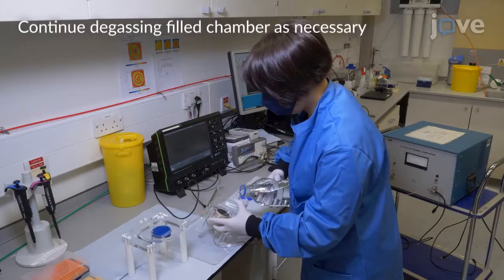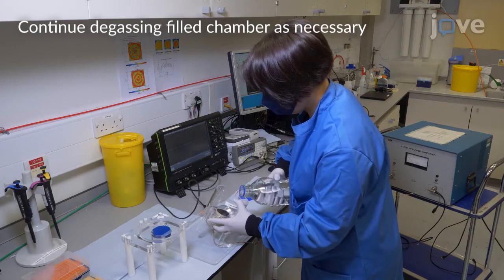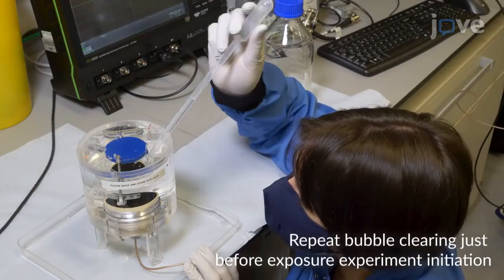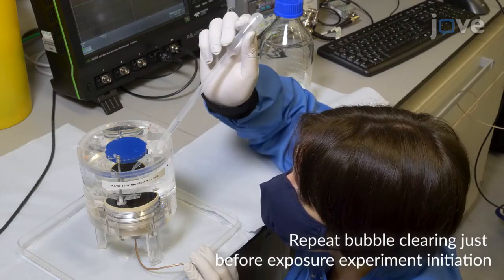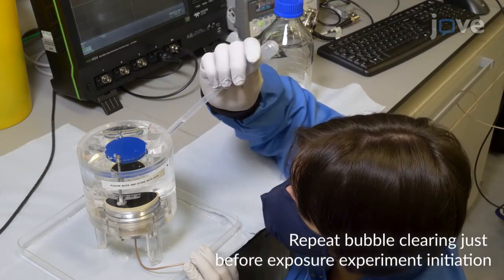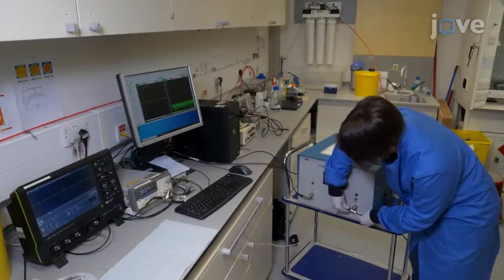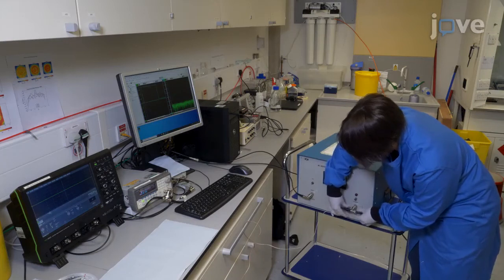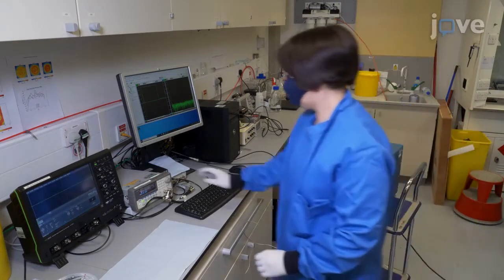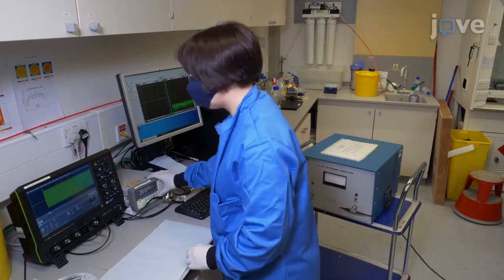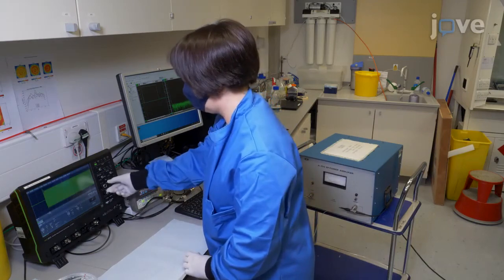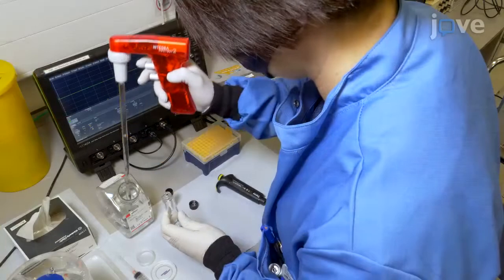Fill the test chamber slowly to minimize the reintroduction of air into the degassed liquid, and immediately clear any residual bubbles from the transducer and medium container surfaces. Allow the ultrasound source power amplifier to warm up per the manufacturer's recommendation so that the gain and output are stable with respect to time.